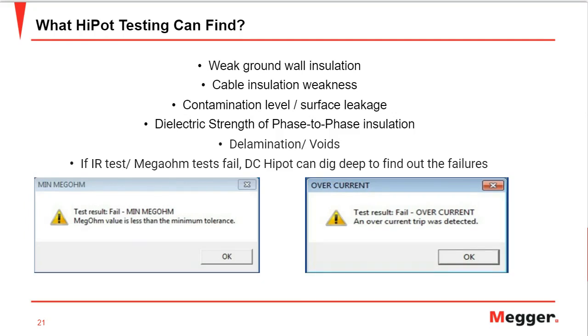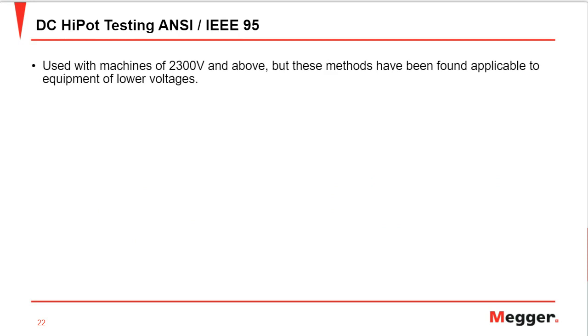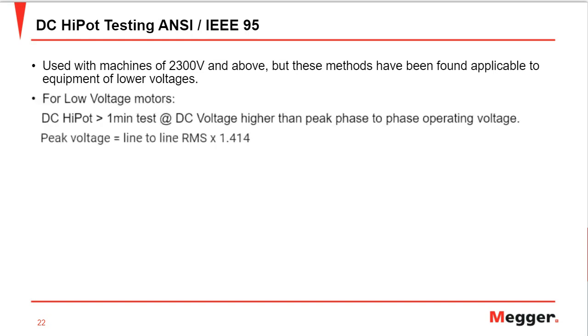We'll discuss something more on the DC high-pot as per the IEEE 95 standard. As far as the IEEE 95 standard is considered, DC high-pot testing is done on machines of 2,300 volts and above. But these methods have been really helpful in finding faults on low voltage motors as well. It's just the voltage that changes whenever the rating of the motor changes.